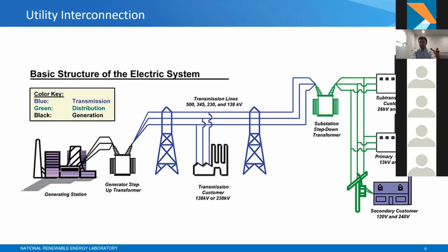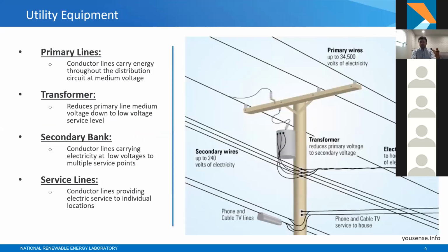And really all of those equipment needs to be able to supply that load that you're going to be demanding. So if there's a new demand coming on your facility, each piece of equipment down the line must have capacity to account for that additional load on the system. Next slide.